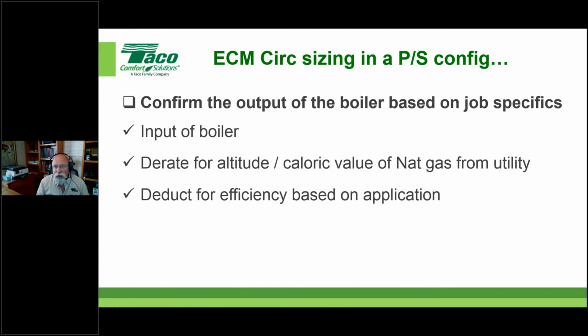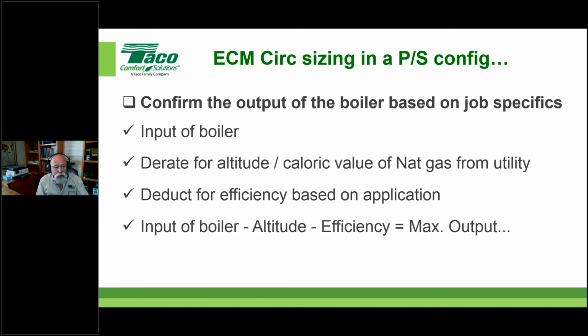sizing. But if you say, well, I'm going to do a bunch of snow and ice melting at high temperature, I'm going to do a bunch of domestic hot water generation at high temperature, et cetera, where those return temperatures won't be as low as they could be on, say, a high mass radiant application, then don't use the AFUE. Use something less, probably in the neighborhood of 86, just over the edge of non-condensing, that sort of thing. So anyway, the input of the boiler minus the altitude minus the efficiency will sort of get you to the maximum output of the boiler, and you could size the pump on that.